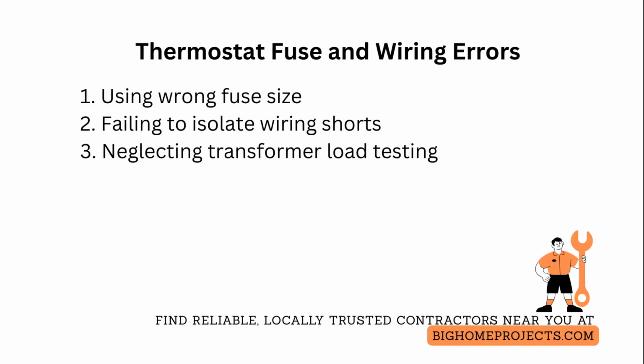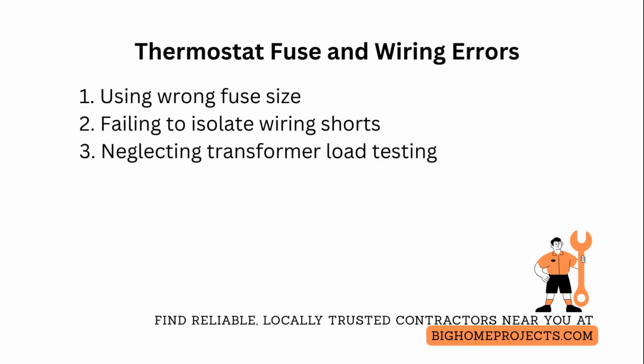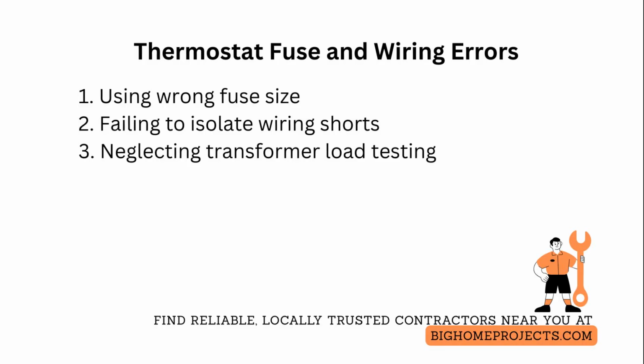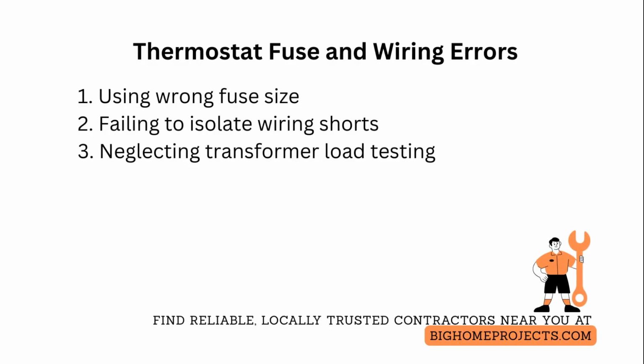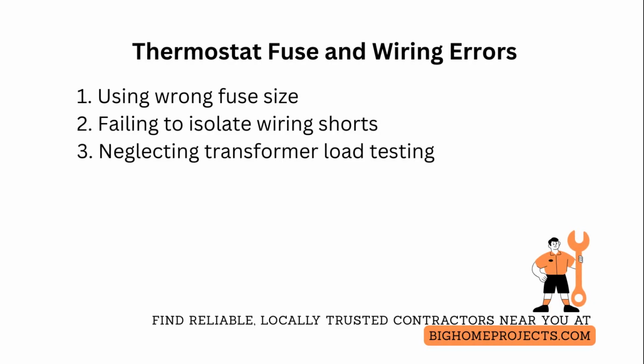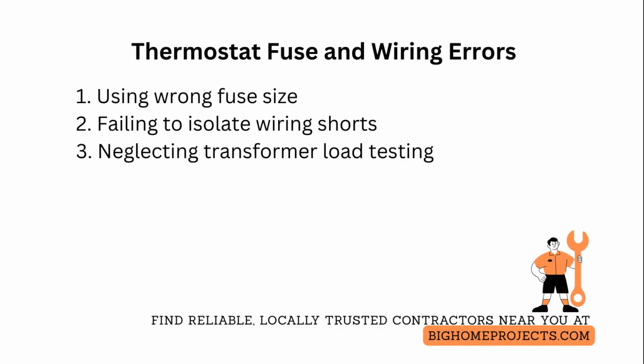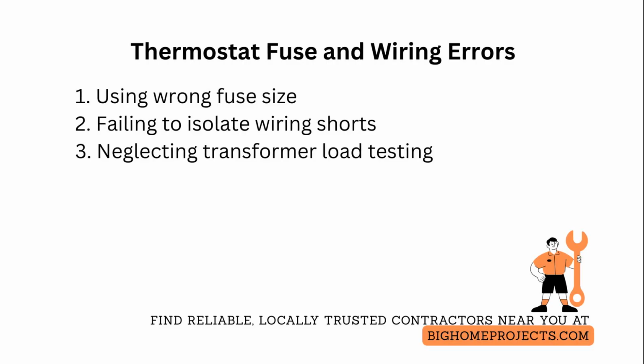One of the biggest mistakes is using the wrong fuse size when replacing blown fuses, which shows up in search queries like thermostat fuse replacement, thermostat blows fuse, and blown 3 amp fuse. The fix is to always replace with the exact amperage and type, source replacements before starting work, and never upsize the rating. One of the next common issues is failing to isolate and identify the shorted circuit.